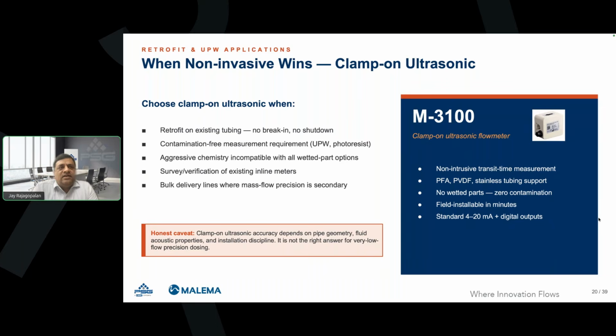So the caveat here is that clamp-on ultrasonic accuracy depends on the pipe geometry, fluid properties, and installation discipline. For example, unlike inline flow meters, which are made at the factory of a vendor, where the calibration is done at the vendor location, in the clamp-on the installation of these devices onto the plumbing is managed by the customer, such as yourself. So the trade-off is that if you're not installing it correctly, obviously it can lead to errors in the device. So, keeping that in mind, in terms of convenience of installation, clamp-on obviously stands out.